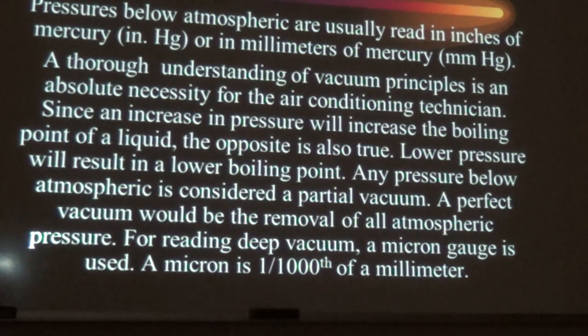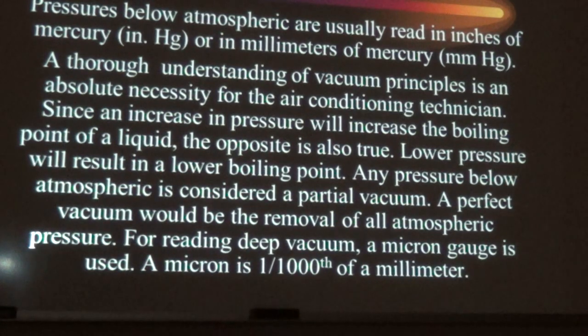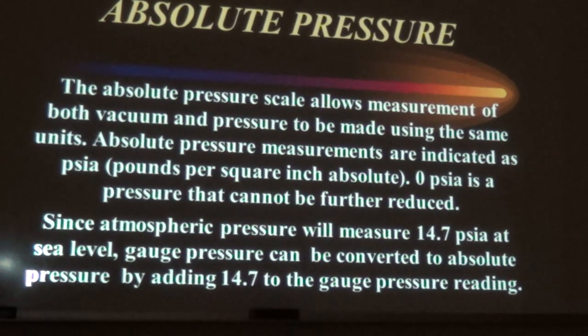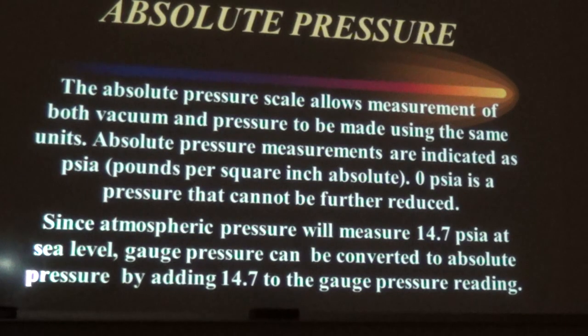Absolute pressure (PSIA) allows measurement of both vacuum and pressure using the same units without conversion — you don't have to add 14.7. Zero PSIA is pressure that cannot be further reduced. Since atmospheric pressure measures 14.7 PSIA at sea level, gauge pressure can be converted to absolute pressure by adding 14.7 to the gauge reading.